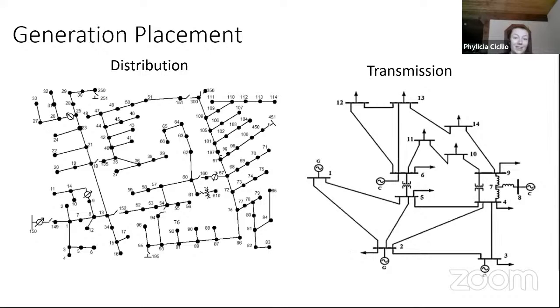Next, we'll talk about generation placement. These are two models of a power system shown as a single line diagram. On the left is a distribution system - these are the lower voltage systems that bring electricity directly to houses and buildings from substations. The system on the right is a transmission system, which is used to take electricity from large generators to the substations. Historically, generation really was only on the transmission grid, and the properties of transmission grids are different than distribution grids, and you can see it here. The transmission system is more meshed and interconnected, and the distribution system is radial - each line goes to a dead end.